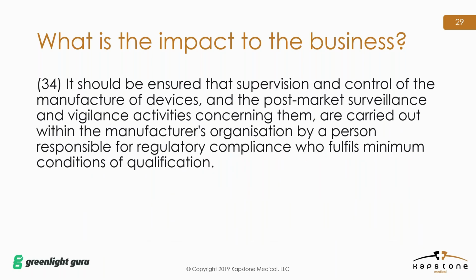So another important requirement is the concept of a person responsible for regulatory compliance who fulfills minimum conditions of qualification. As we know from ISO 13485:2016, competence is a hot topic and a hot word. The EU MDR is requiring similar competences to be shown in place in the post-market surveillance, as well as other specific references to qualifications, such as in the clinical evaluation.